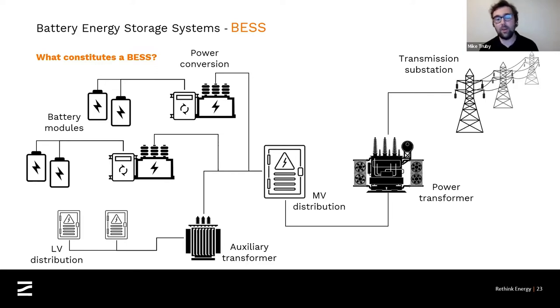From there, we also have some kind of auxiliary distribution system, and this is basically to provide small power, lighting, and low voltage power to all of the applications that are needed to support the batteries. Management of the heating and cooling of the batteries, ventilation of the batteries, control systems for the site, telecommunication systems. And in addition to that, the final and most important component of all of this is the actual battery modules themselves. When we talk about BESS, we're actually not just talking about batteries, but a number of devices connected together to allow those batteries to connect to the grid. So if I have the next slide, please, Simon.